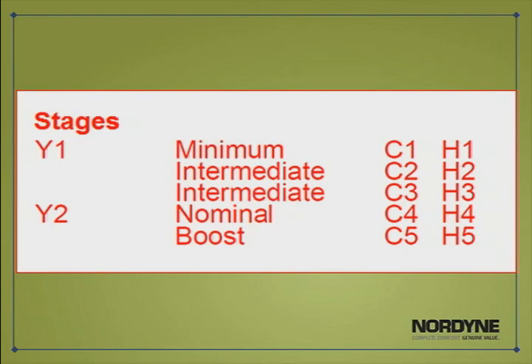In heating mode, the condenser receives a Y1 signal from the indoor thermostat. The outdoor fan motor again will start and run for 1 minute before the compressor starts. In most cases, the system will start at stage H2. With a Y1, Y2 call from the thermostat, the condenser will stage up to H4 and run for 45 minutes. If the thermostat is still calling after 45 minutes, the unit will go into boost mode, stage H5.